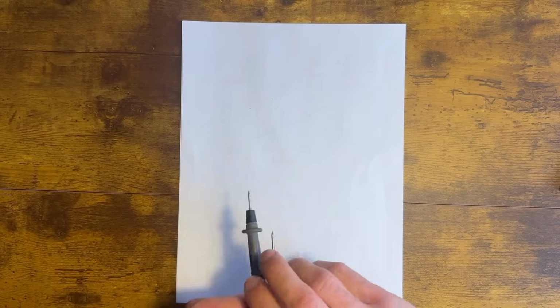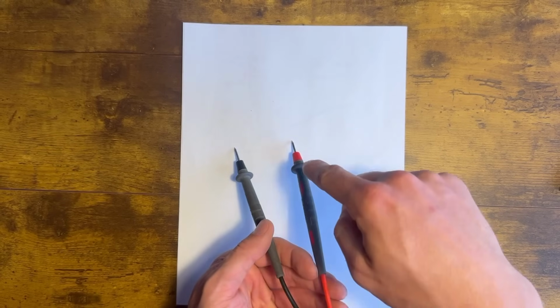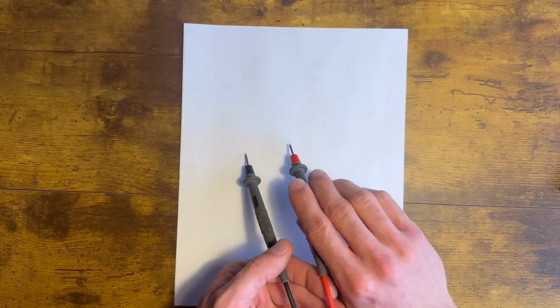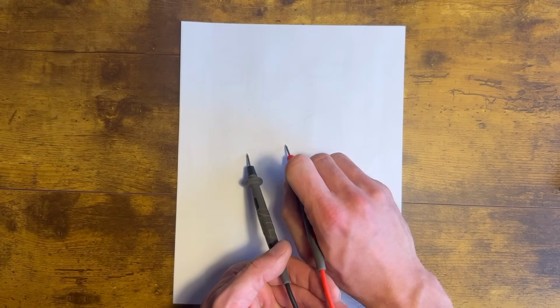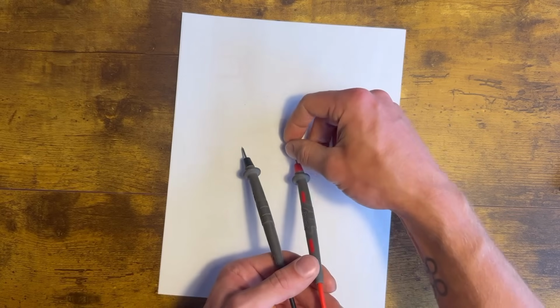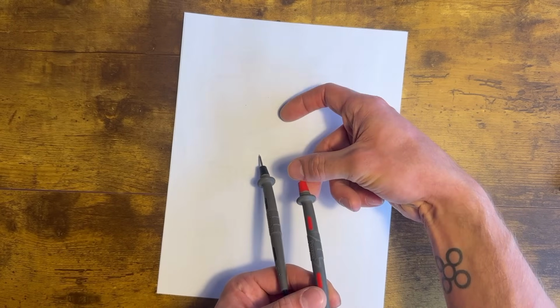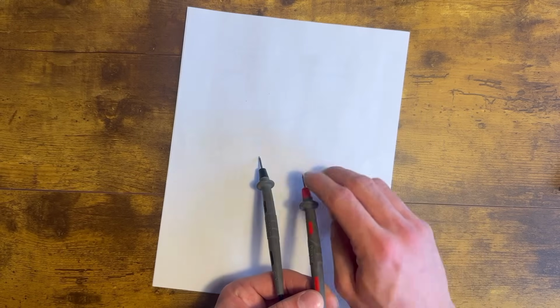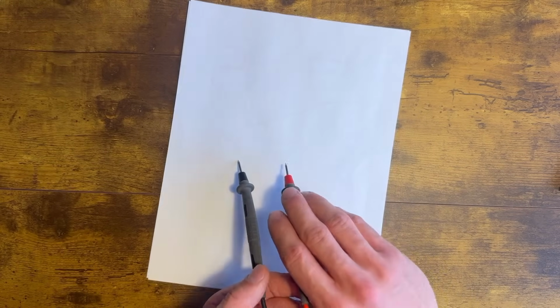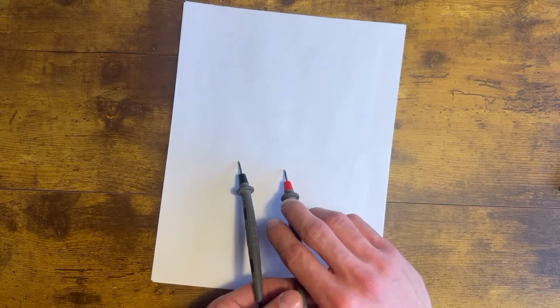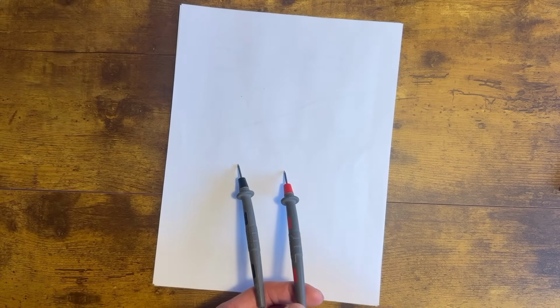This can also happen at the probe tip. If the meter shorts out completely, or has an arc inside of it, the noise might make the person holding it start to pull the probes away, which can start to draw an arc off of whatever it's connected to, a bit like a welder, but way more power, and can have the same effect. It explodes in an arc flash, but without even the containment of the meter body.